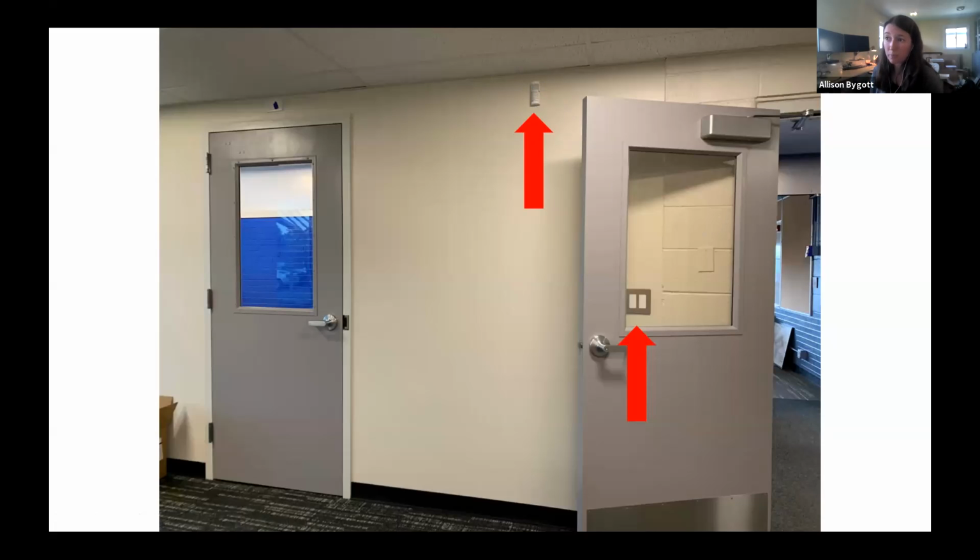So sometimes I think when we're picking these products, we don't realize how hard it is later to verify that they're really working. On this job, I don't know if this manufacturer would call this a networked lighting control system. In my opinion, it's not. It's very much standalone. Even though I have a fancy app on my phone to control things with, you have to go stand in every room and toggle everything to see how it's going to sequence. So it takes a lot of time.